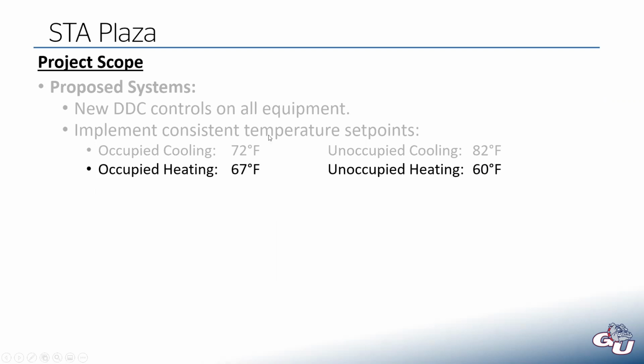And it should be noted, these temperatures on the cooling and heating side are a bit lower than normal. Normally, we do an occupied heating set point of about 70 degrees. But in this type of facility, you think of all these people coming into the building to wait for their bus. They're wearing their outside clothes, meaning coats and hats and gloves, and that all plays into the comfort of the building. So it's not unheard of to maintain the building at a lower temperature if you're expecting the occupants to be wearing bulkier clothes. And then, of course, we have a 5-degree dead band between these two systems, where if we're between 67 and 72, nothing should be going on.